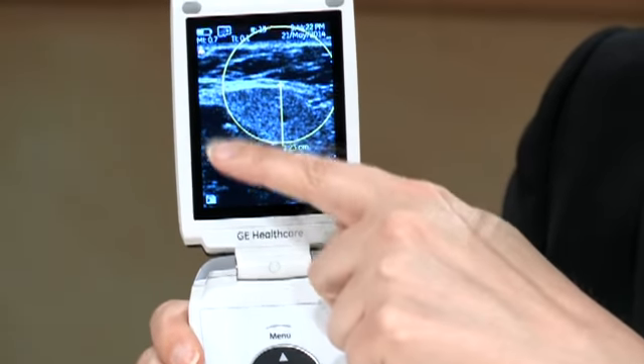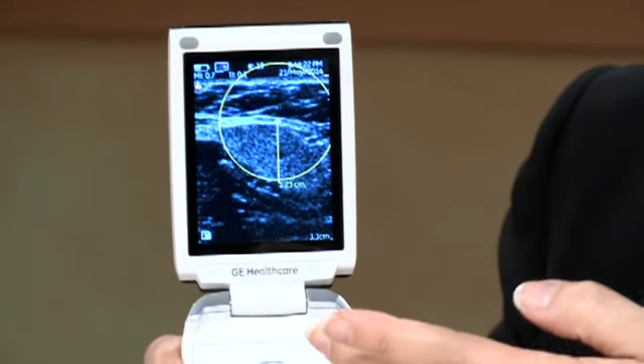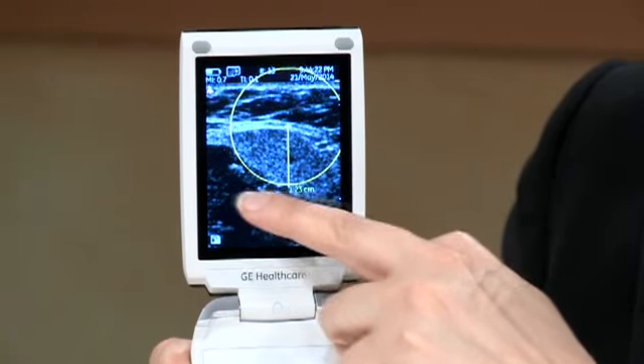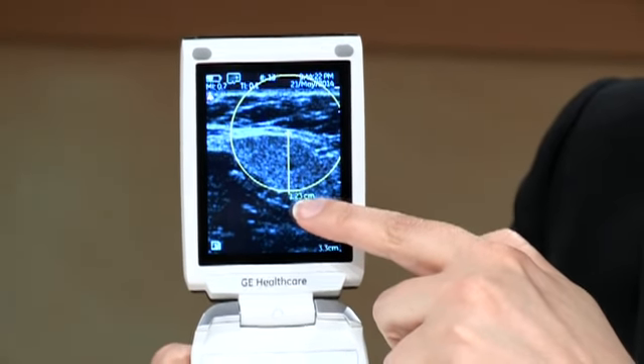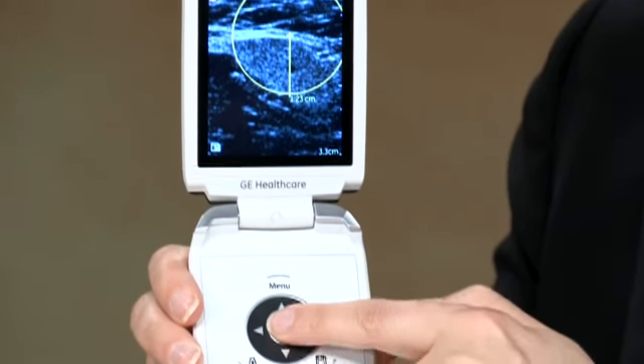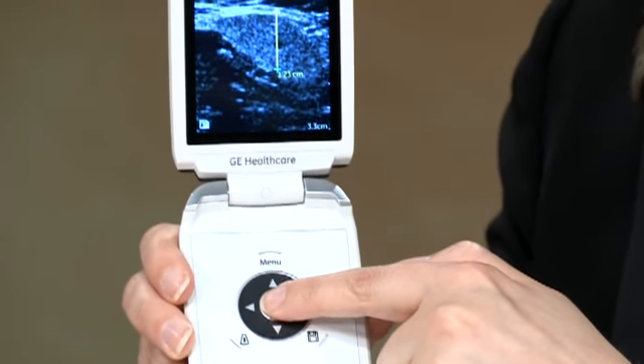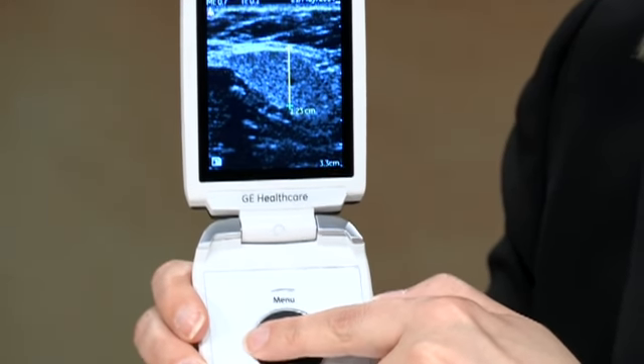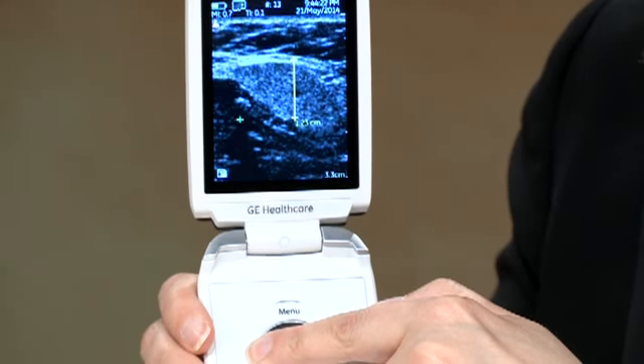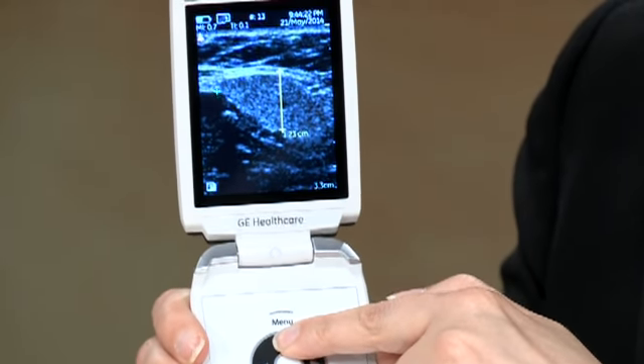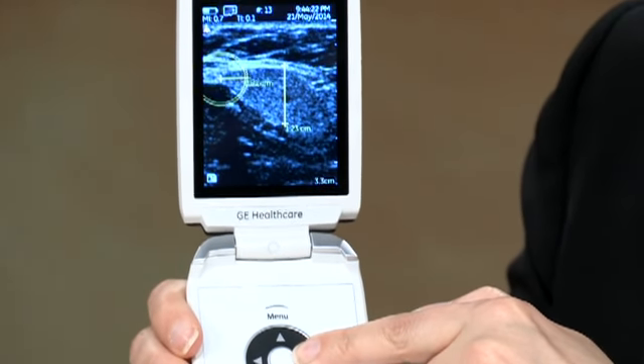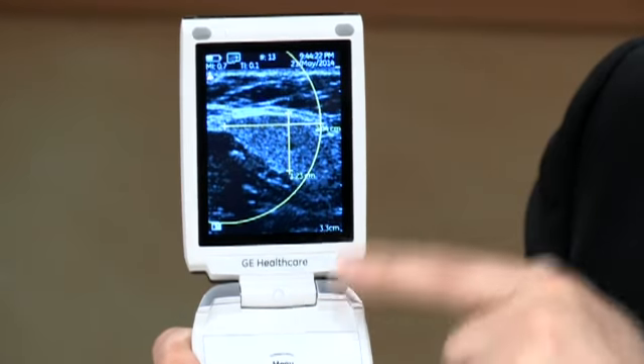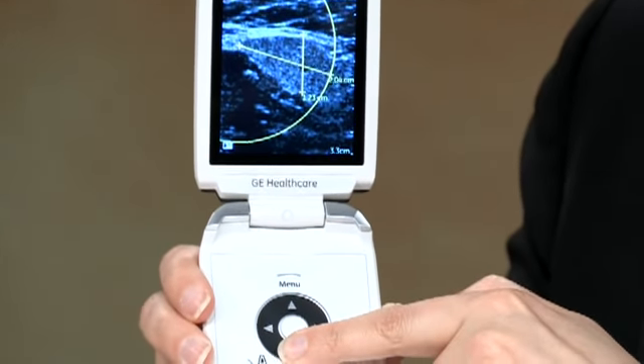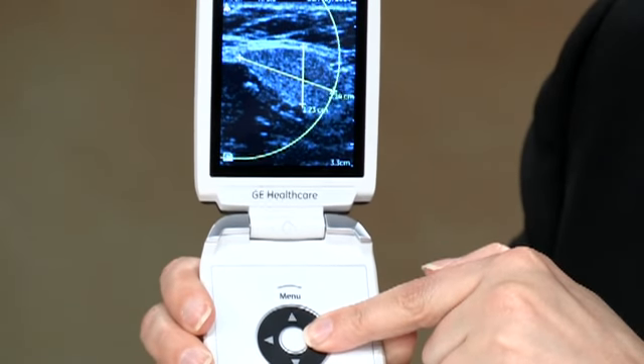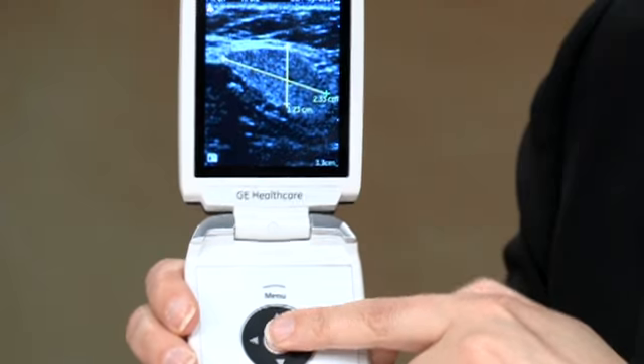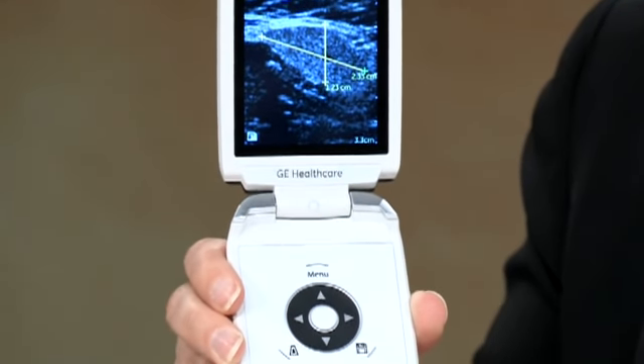You will see that this radius display appears. The intention is to reduce keystrokes so that any distance along that radius would be the same as the number displayed. However, if you want to anchor that caliper, the radius disappears and then a second green caliper appears. This second caliper can be placed using the arrows, just like we did for the first caliper. To move the caliper along the radius, continue to use the up and down arrows. Select to anchor. Up to 8 measurements can be performed on a Vscan image.